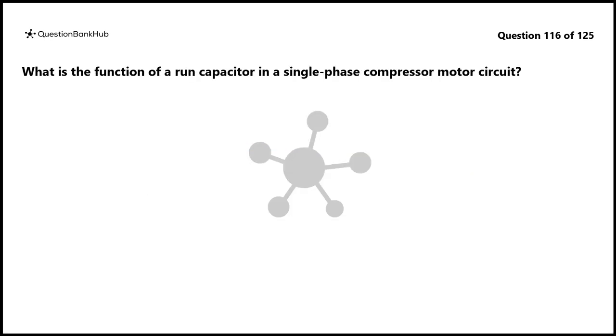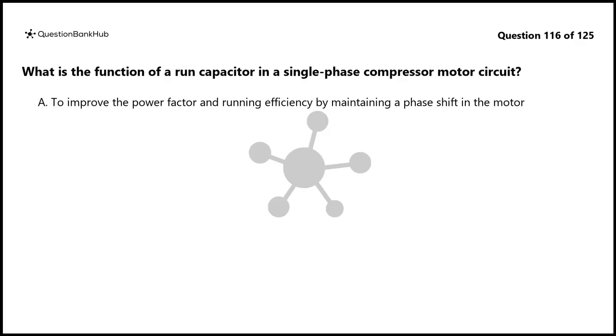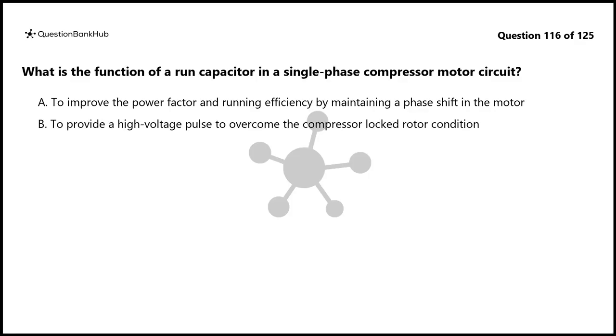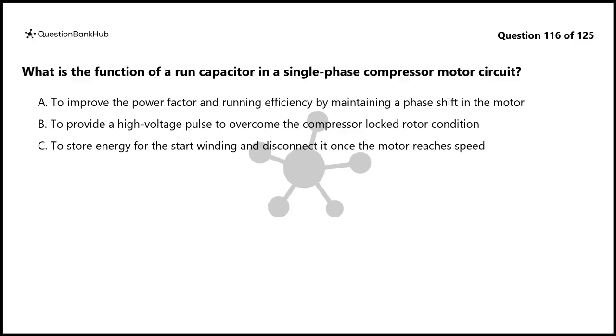Question 116. What is the function of a run capacitor in a single-phase compressor motor circuit? A. To improve the power factor and running efficiency by maintaining a phase shift in the motor. B. To provide a high voltage pulse to overcome the compressor locked rotor condition. C. To store energy for the start winding and disconnect it once the motor reaches speed. D. To regulate the supply voltage to protect the compressor from power surges.